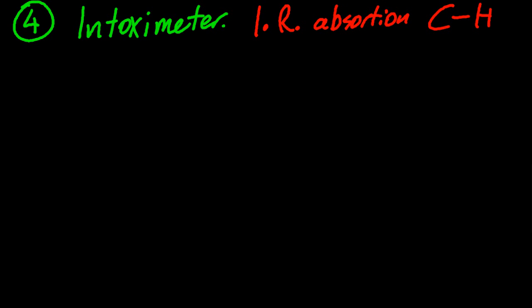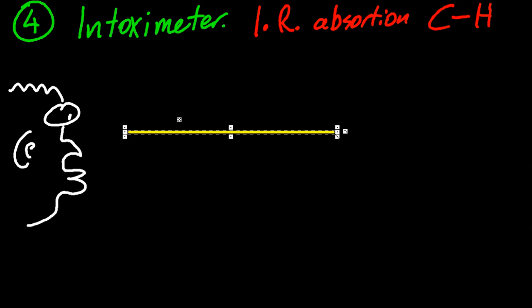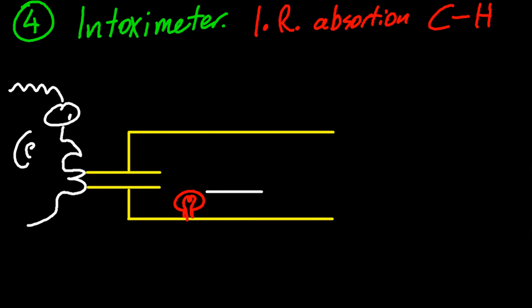Number four is an intoximeter. There are two sorts of intoximeter you need to know how to use, or the theory behind them. The first is an infrared absorption intoximeter. It works on the carbon-hydrogen bond that's present in alcohol. Let me just draw out an extremely simple schematic of an intoximeter.